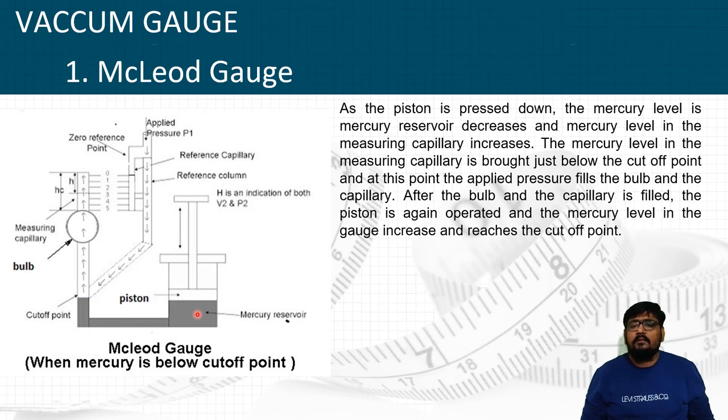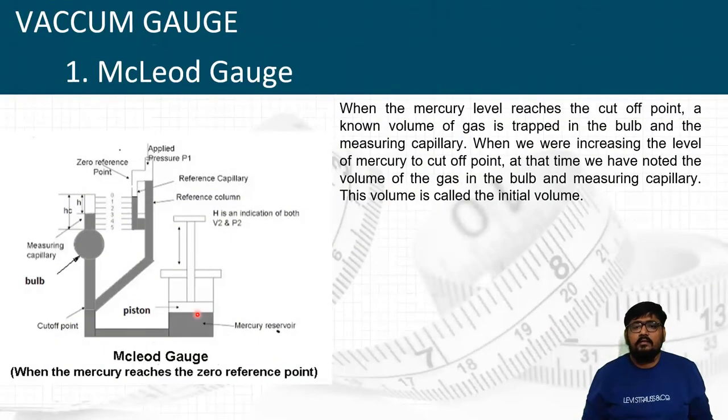After the bulb and capillary are filled, the piston is operated again and the mercury level increases to reach the cutoff point. When the mercury level reaches the cutoff point, a known volume of gas is trapped in the bulb and the measuring capillary. At this stage, the volume of gas in the bulb and measuring capillary is noted as the initial volume V1. We now know the initial volume V1 and the initial pressure P1.